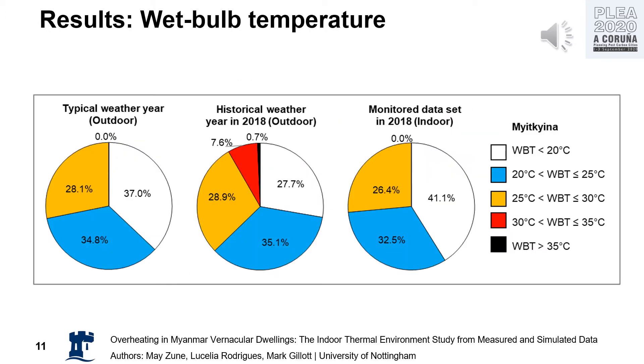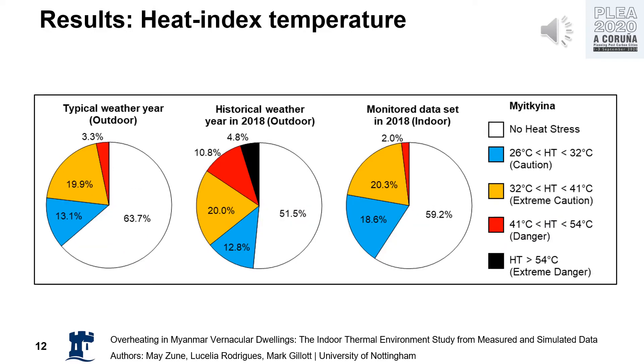In 2018, the outdoor wet-bulb temperature above 30 degrees Celsius significantly increased, as seen in the red color on the chart. In contrast, the indoor temperature for 2018 and the typical weather year remained below 30 degrees Celsius. In 2018, the outdoor heat index reached an extreme danger state shown in black, but the indoor heat index only reached a danger state, and only in a very small proportion.